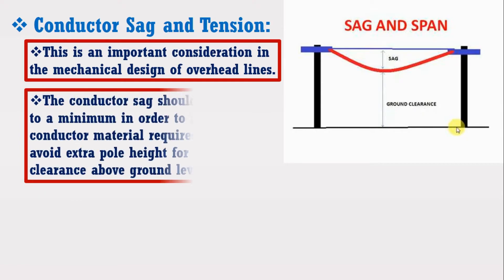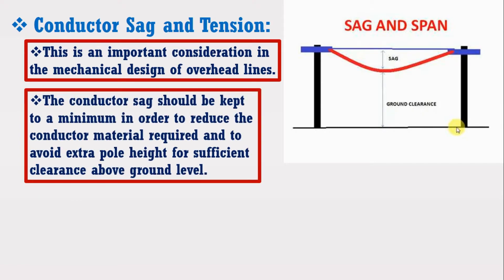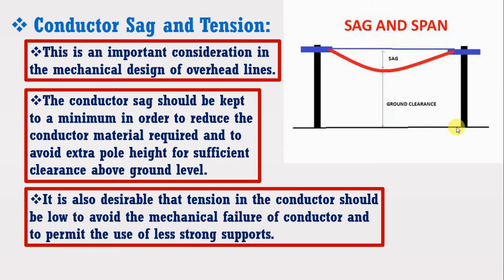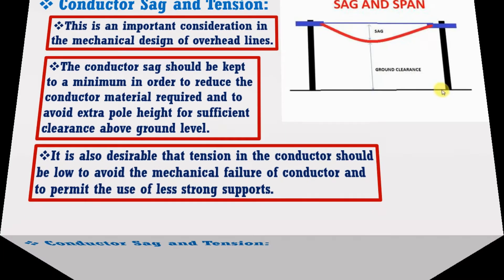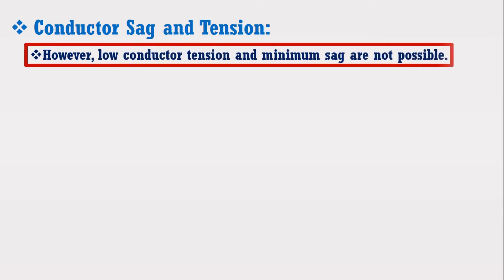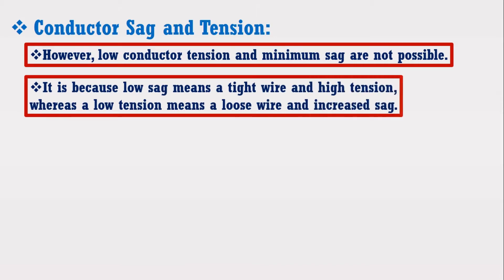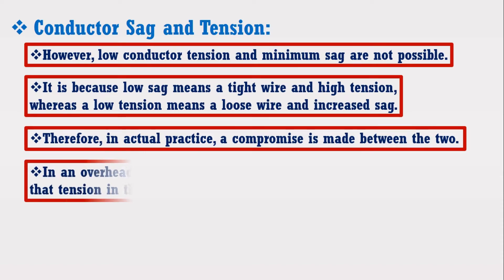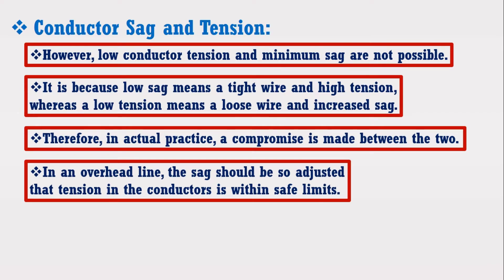The conductor sag should be kept to a minimum in order to reduce the conductor material required and to avoid extra pole height for sufficient clearance above the ground level. It is also desirable that tension in the conductor should be low to avoid mechanical failure and to permit the use of less strong supports. However, low conductor tension and minimum sag are not possible simultaneously. Low sag means a tight wire and high tension, whereas low tension means a loose wire and increased sag. Therefore, in actual practice a compromise is made between the two. In an overhead line, the sag should be so adjusted that tension in the conductor is within safe limits.